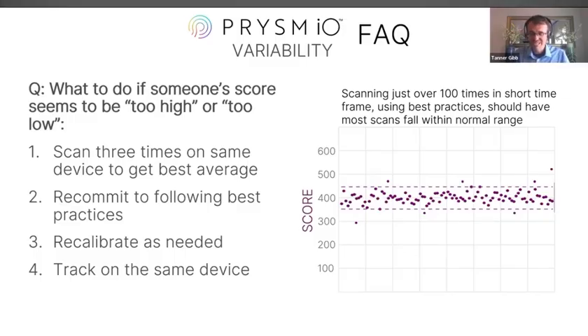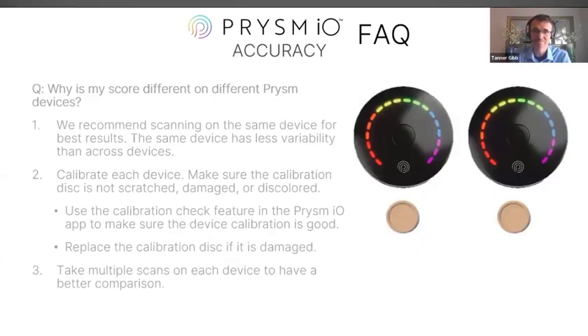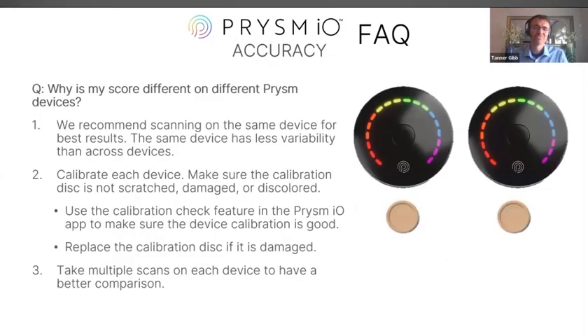It's a very detailed detection practice to be able to minimize the other stuff and focus in on these carotenoids, which is the purpose of this device, to be able to measure those with accuracy. Why is my score different on different PRYSM devices? Well, we want to recommend, firstly, scanning on the same device for the best results. That is always going to be our standard recommendation. The same device has less variability, in other words, better precision, than across devices.